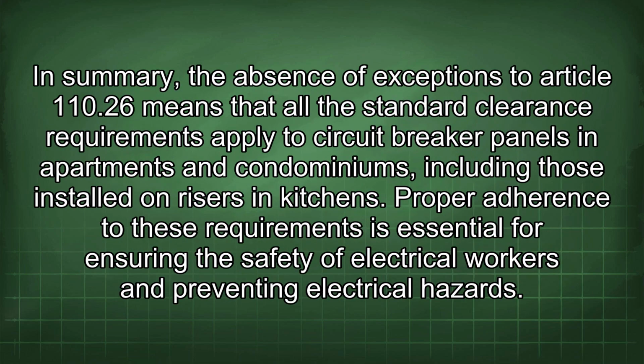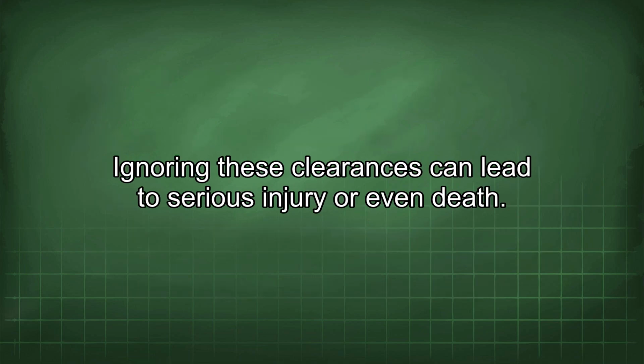In summary, the absence of exceptions to Article 110.26 means that all the standard clearance requirements apply to circuit breaker panels in apartments and condominiums, including those installed on risers in kitchens. Proper adherence to these requirements is essential for ensuring the safety of electrical workers and preventing electrical hazards. Ignoring these clearances can lead to serious injury or even death.